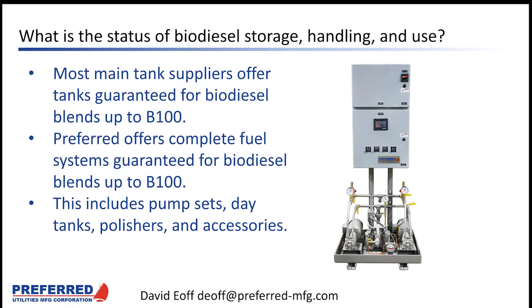So what is the status of the technology around biodiesel storage, handling, and use? Preferred and a few of the main tank suppliers have tried to be ahead of the curve and offer equipment rated for B100. Preferred offers complete fuel systems guaranteed for biodiesel blends up to B100. This includes the pump sets, day tanks, polishers, and all the accessories that go in between. You do need to specify biodiesel compatibility when you order from Preferred. Our standard fuel systems include brass and bronze components, but we replace them when we're designing for biodiesel. Very soon, our equipment will have unique part numbers for the equipment that's guaranteed for biodiesel.